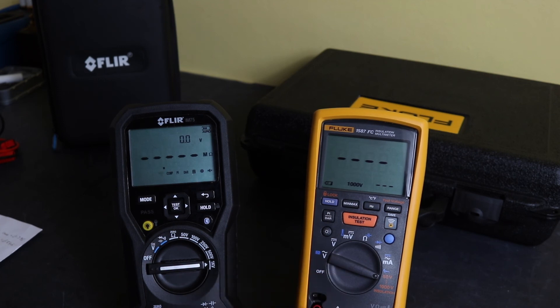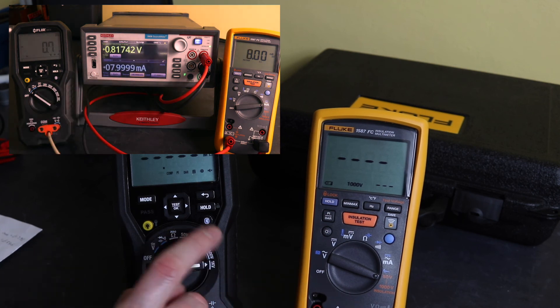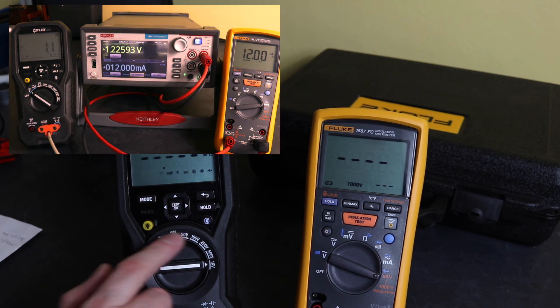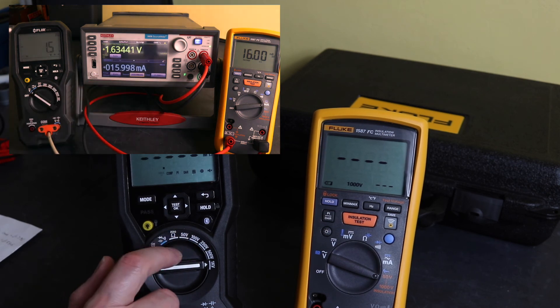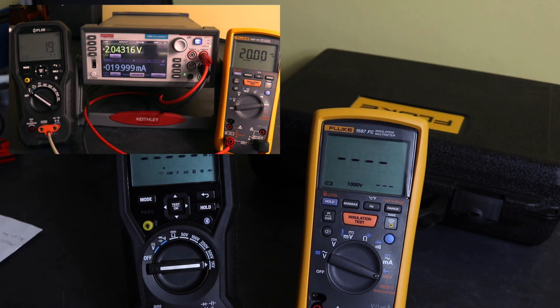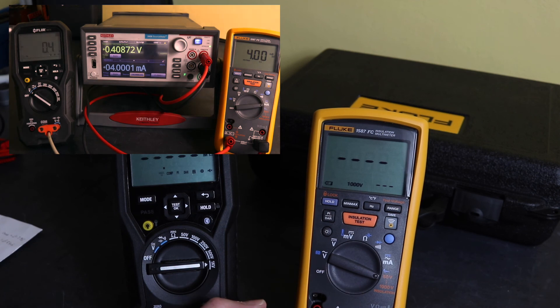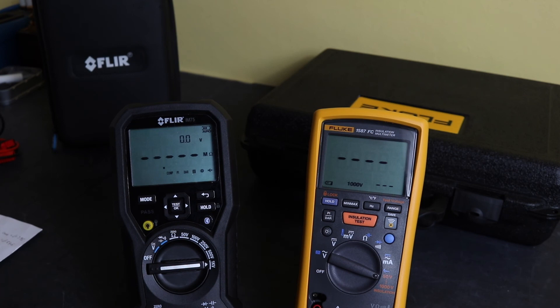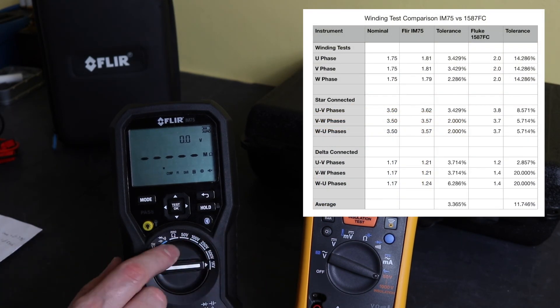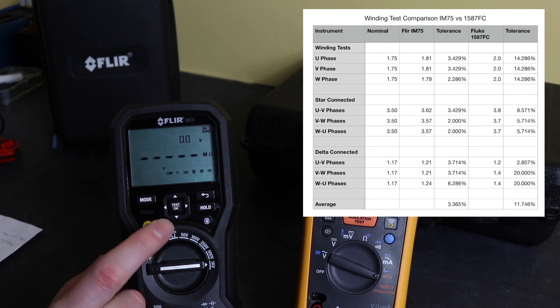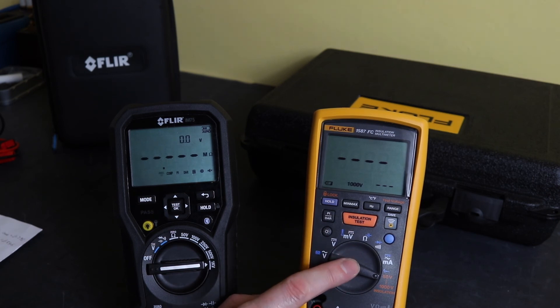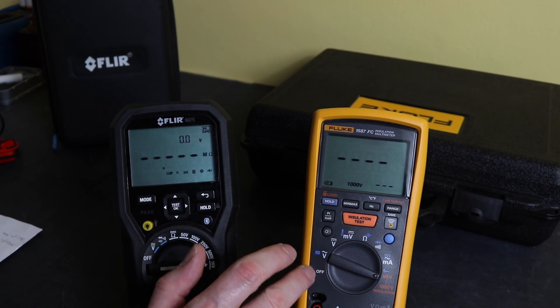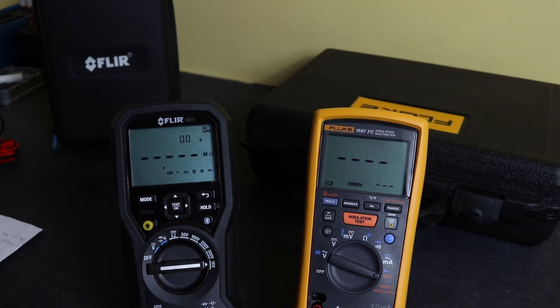So back to the accuracy tests. Another aspect where the Fluke outperforms is on transducer tests, which is quite important to me having the current function on that. So much better than using the voltage function on the Flir with a load resistor, because the DC millivolts on this instrument lacks a fair bit of resolution in comparison to a lot of other instruments and certainly in comparison to the current measurement capability of the 1587 there. Where the IM75 starts to get its own back in the accuracy stakes is with the 200 milliamp test current. I'm testing the winding simulator with this instrument using that function. Much better reading, much more accurate, much more resolution. That is one aspect where the Fluke does fail to perform. Resistance readings on the winding simulator were quite a way out on this instrument in comparison to the others, but overall the accuracy does go to the Fluke 1587 FC there.